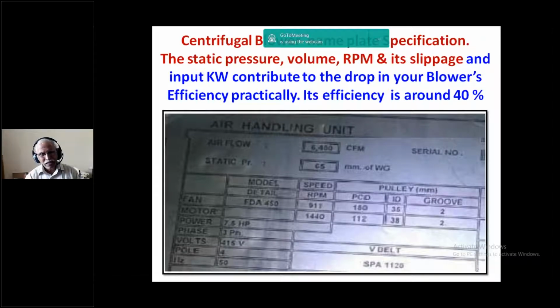Why I am talking about the Pascal now is, you just go through the nameplate. The study of the nameplate itself will give the equipment specifications, what is the in and out of the equipment. Now, all the while the industries have been checking for all the blowers, not the compressors, for the blowers, they are talking in terms of the flow only, in terms of CFM or meter cube per hour. This is one important thing. But let us take this case of this nameplate, 6400 CFM at 6.5 mm of water column. That is, sorry, 65 mm of water column. Almost it is equal to 650 Pascal. See, this Pascal is more important. This defines the static pressure in the system, what is generated, what is distributed, and what is taken at the end point. This is where we are going to concentrate.